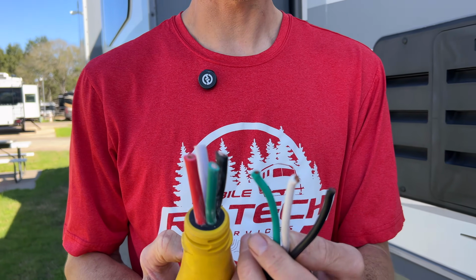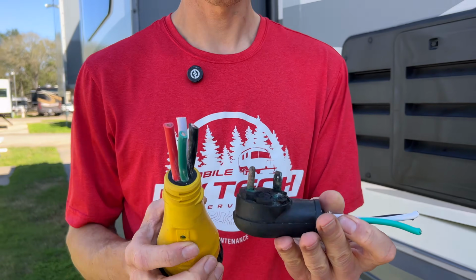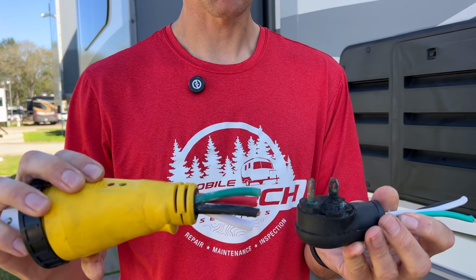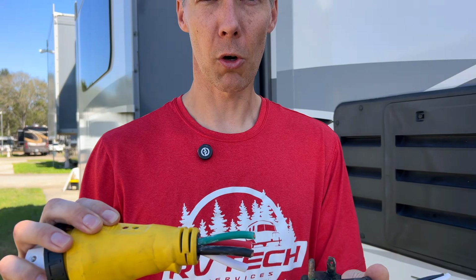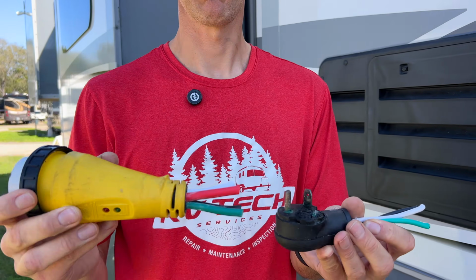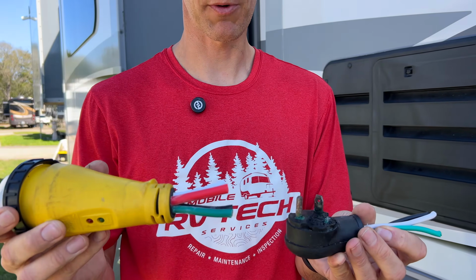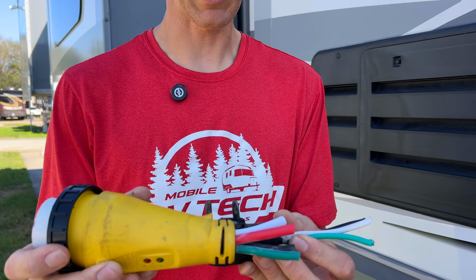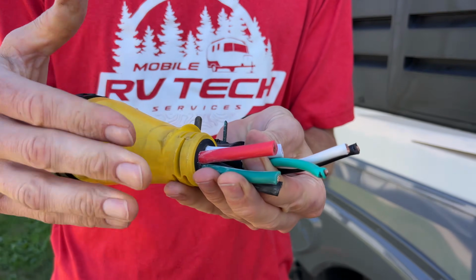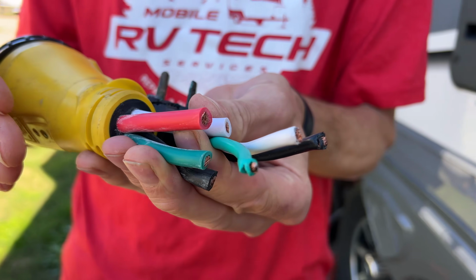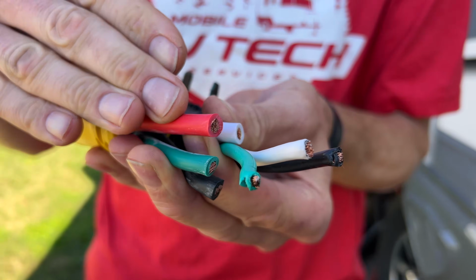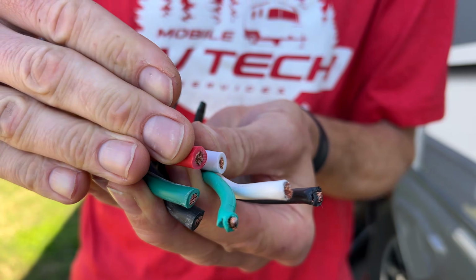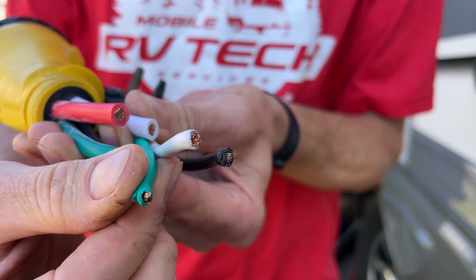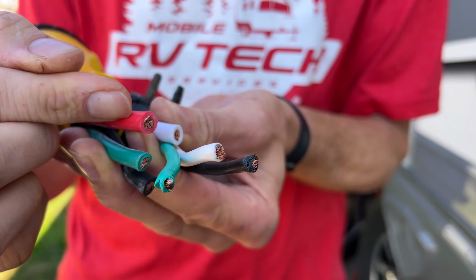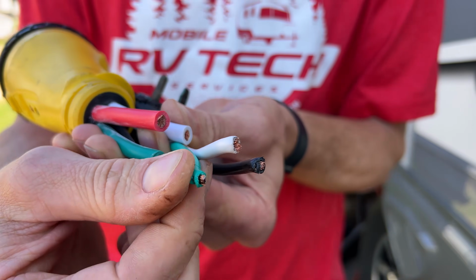So what you're doing when you plug a 30 amp plug into a 50 amp outlet is removing the safety restriction, because you have 50 amps of potential power going through that 30 amp cord. Picture this like a water hose: you're shoving all this water down the hose and then pinching it down and restricting it. That's going to create heat when you have too much pressure on the smaller hose.